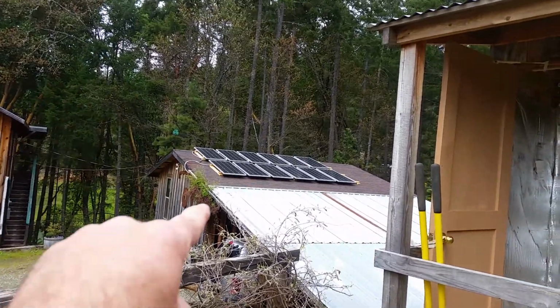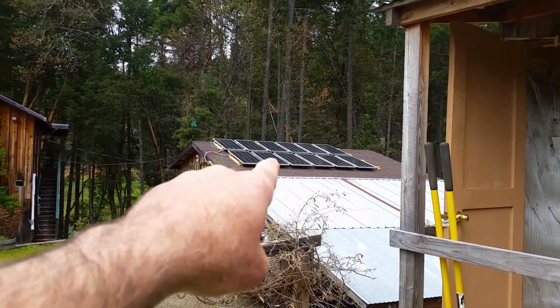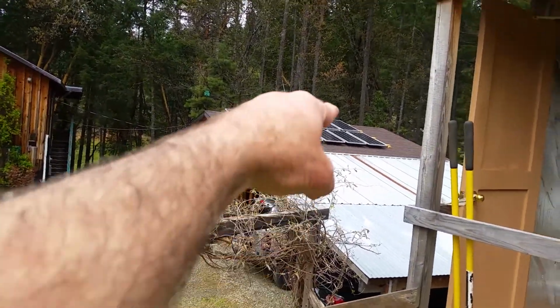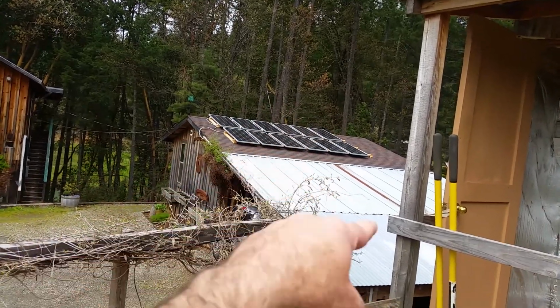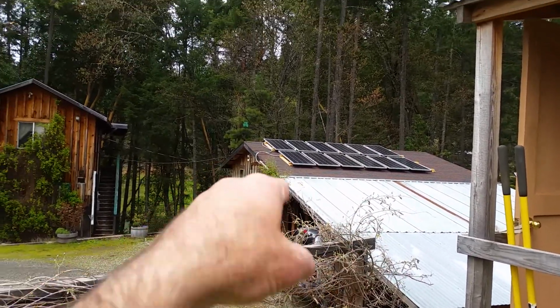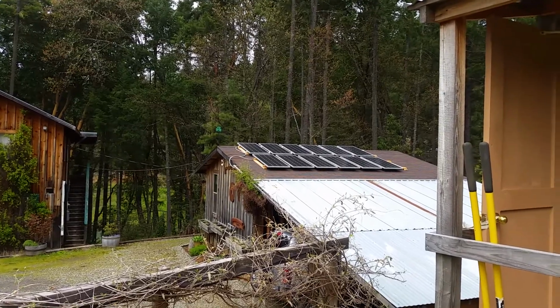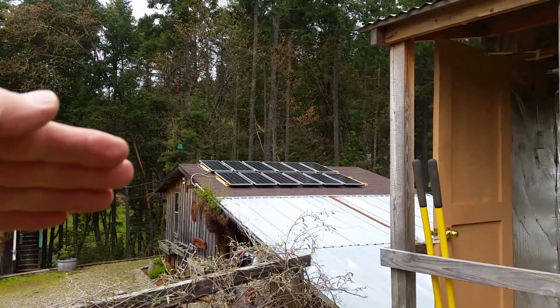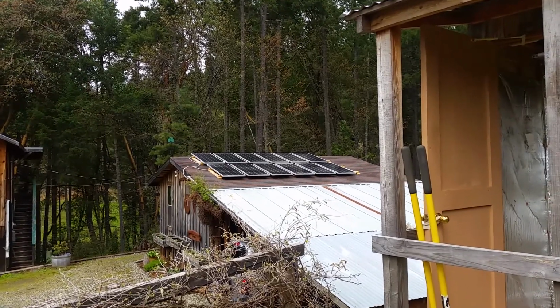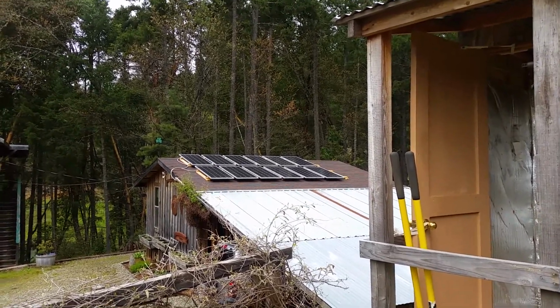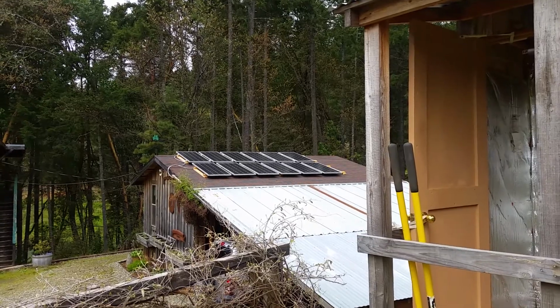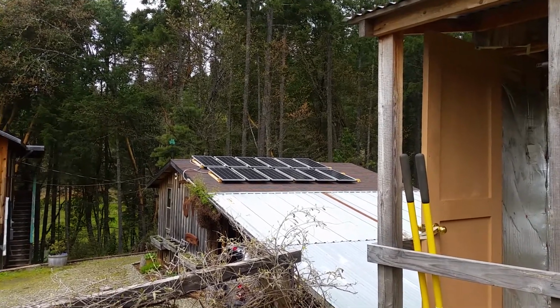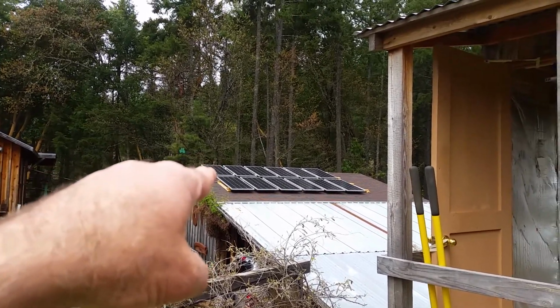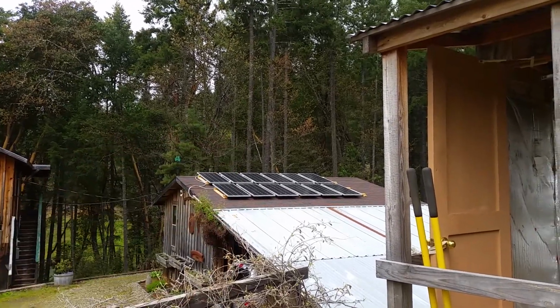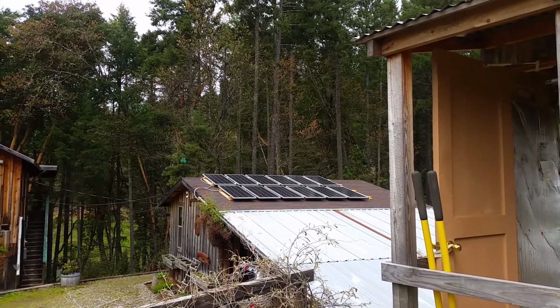That's safe, protected with fusing at both ends, all in the right wire size, etc. But when you start putting solar panels on the roof of a structure that has a bedroom in it, plus my wood storage, my cars, and my wife's beauty salon, when something goes up on the roof you'll notice everything's in conduit, in the right junction boxes, all the right wire size and right kind of wire. You just don't take any chances. MPPT, higher voltage, that's no joke, and you want to make sure you get it right.